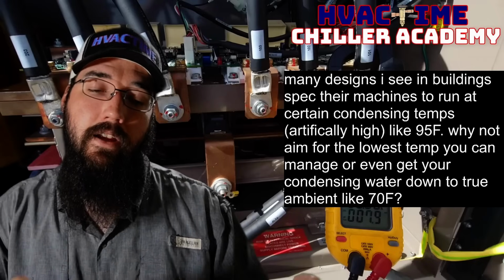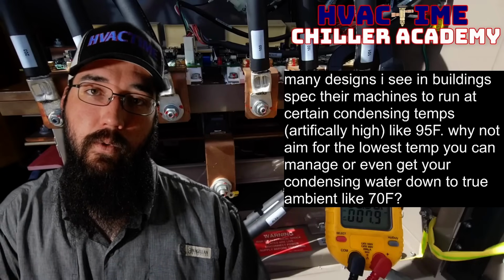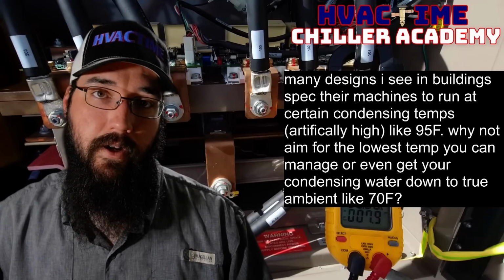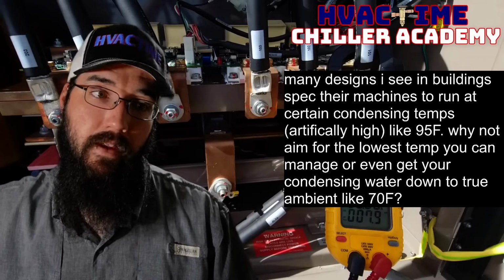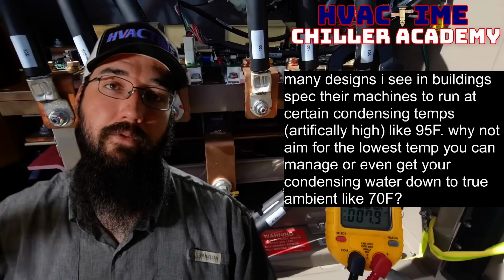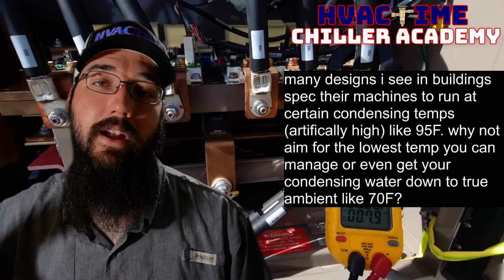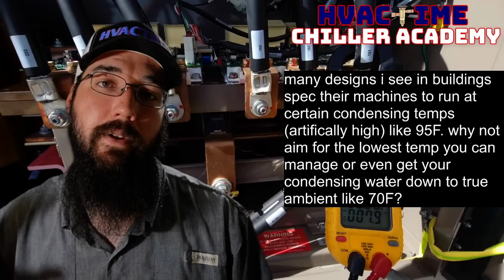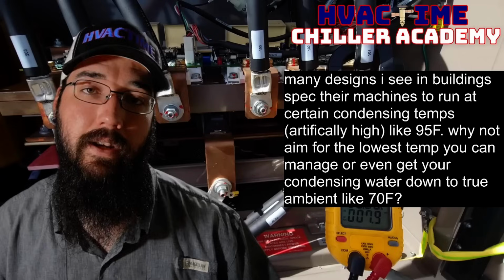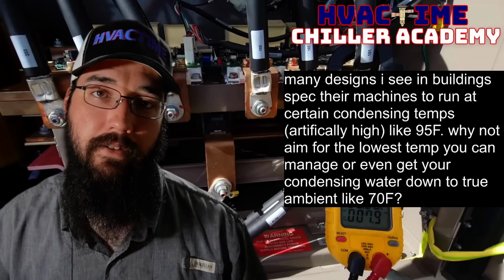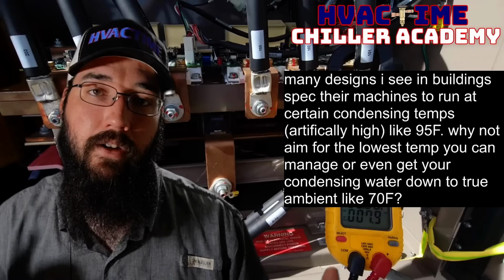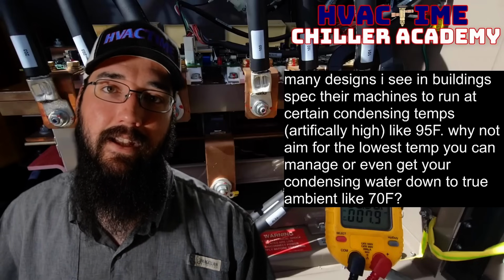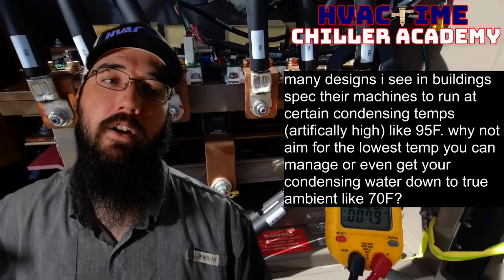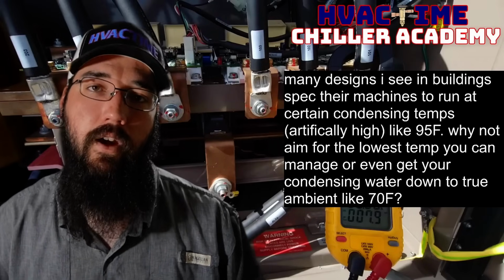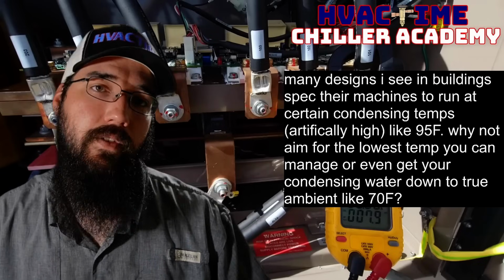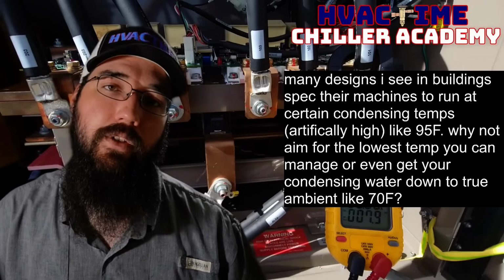At that point, it'll control that algorithm, wet bulb plus 5 equals your output within this window. The control system can vary the fan accordingly, and then we're not putting any more load on the fan than we absolutely have to to make leaving water set point, which allows us to not have to run the fan at 100% all the time and still get the maximum amount of leaving water temperature, the lowest value we can get for that chiller.